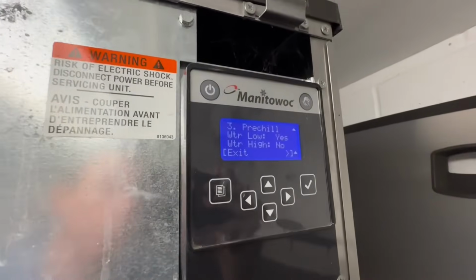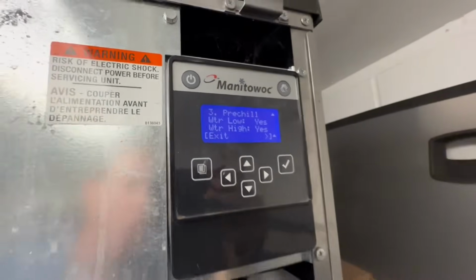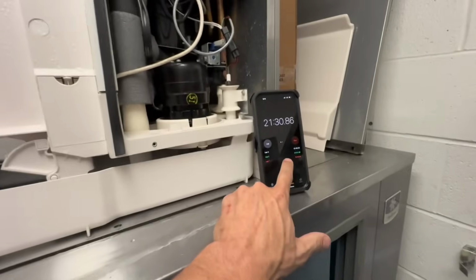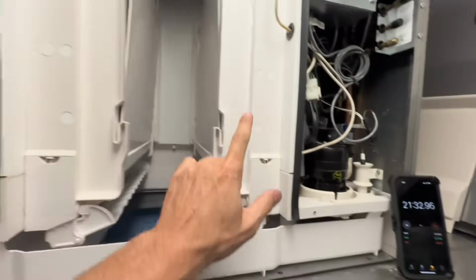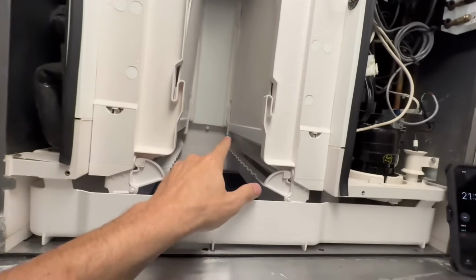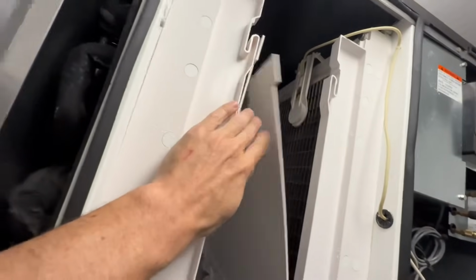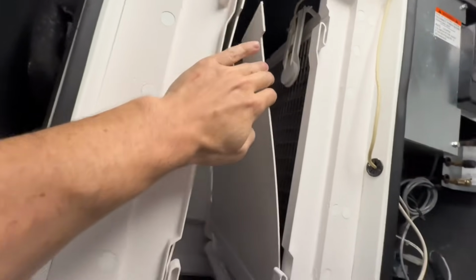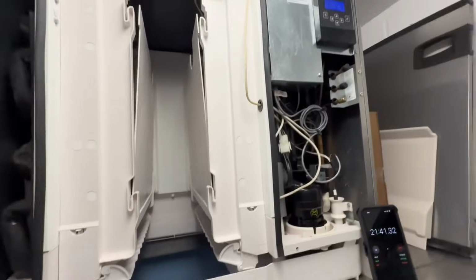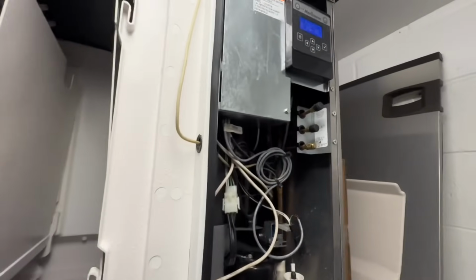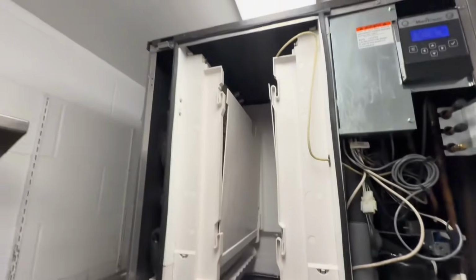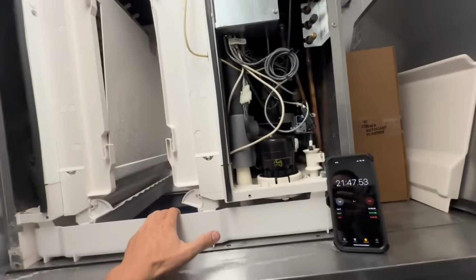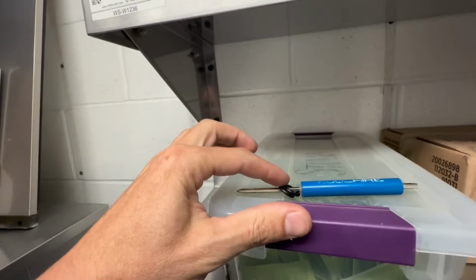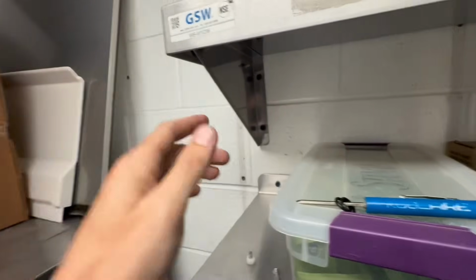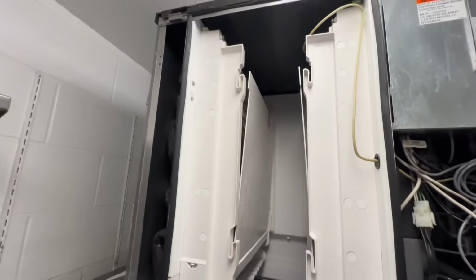Water low just went from no to yes, and then water high just went from no to yes. We haven't even come out of pre-chill yet. We're still in pre-chill, haven't gone into freeze, and that's a good sign. That means that the water filters are the issue. I'm going to close this up and talk to the customer about replacing the filters.